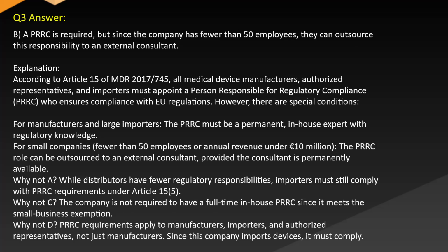Answer: B. A PRRC is required, but since the company has fewer than 50 employees, they can outsource this responsibility to an external consultant. Explanation: according to Article 15 of MDR 2017/745, all medical device manufacturers, authorized representatives, and importers must appoint a person responsible for regulatory compliance (PRRC) who ensures compliance with EU regulations. However, there are special conditions. For manufacturers and large importers, the PRRC must be a permanent in-house expert with regulatory knowledge. For small companies, fewer than 50 employees or annual revenue under 10 million euros, the PRRC role can be outsourced to an external consultant, provided the consultant is permanently available. Why not A? While distributors have fewer regulatory responsibilities, importers must still comply with PRRC requirements under Article 15(5).